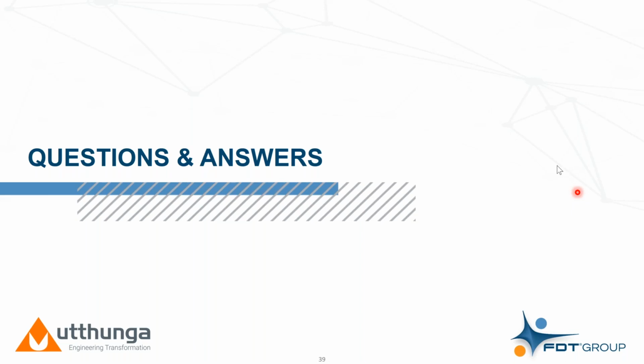So there's other methods, but generally, if you're an OPC UA client, you should be gating your data access requests. And I think this is where Pub Sub is very nice, because you don't have to keep hitting the server to get data refreshes. You'll be informed when there's a data change. And in other cases, the DTM itself may throttle that access. But as always, these are very complex network environments.